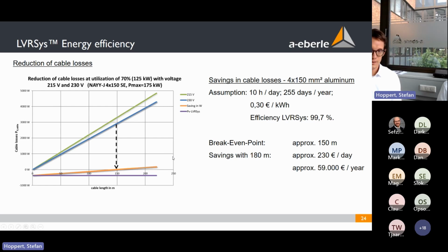On the right side, we see a short calculation example. If you have 180 meters and it works 10 hours per day, 255 days a year, and you have a power cost of 0.3 per kilowatt hour, then you can save 230 euros each day, or per year about 60,000 euros. This sounds quite a lot, and it should give you an idea of how much you can improve the efficiency of the total devices. And besides this, if you have a proper voltage, you even save money if your cable length in the whole factory is quite long.